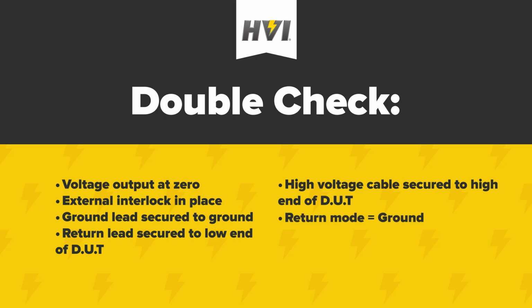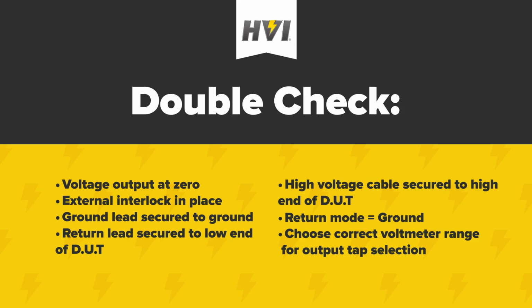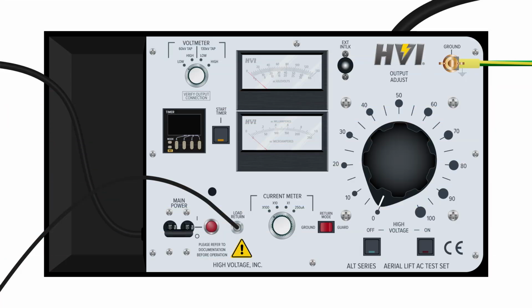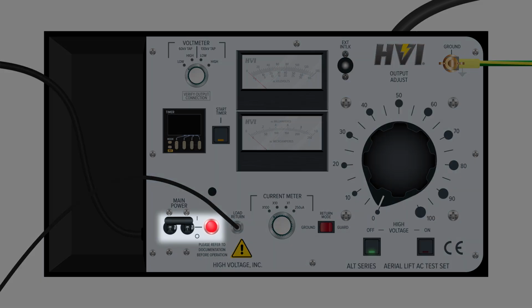Check that the return mode switch is set to ground position. Check that the voltmeter range matches the output tap selection. Check that the current meter is at the highest range setting. Turn on the main power button. When the device is initially powered, the main power light will illuminate red.